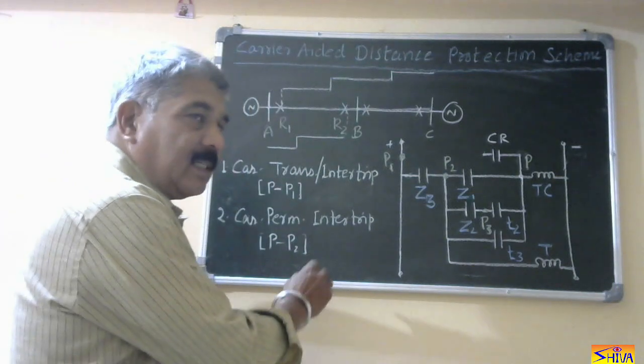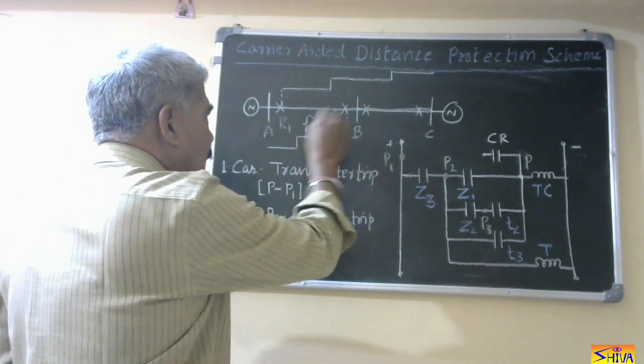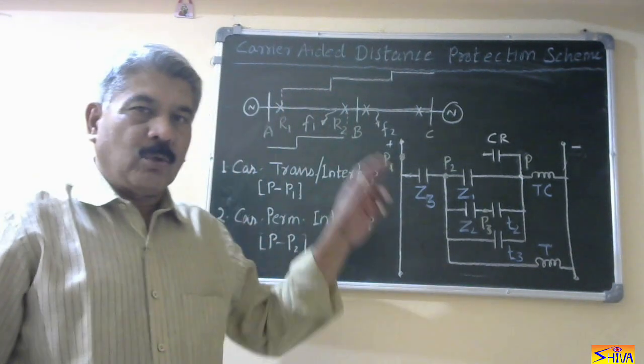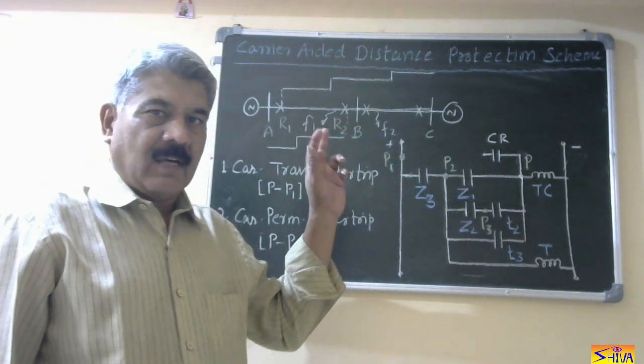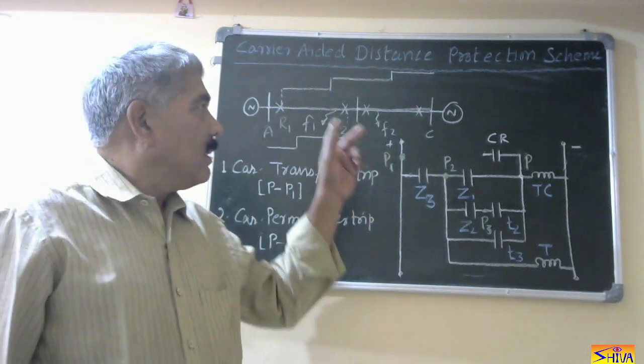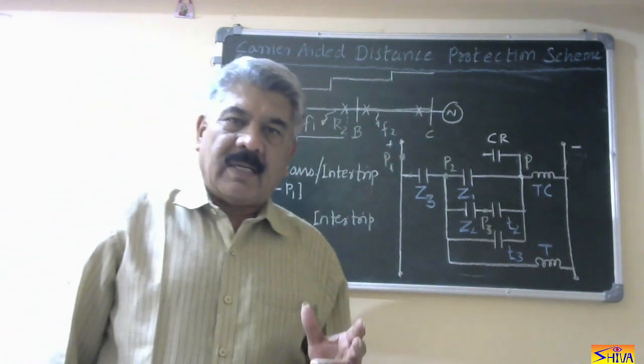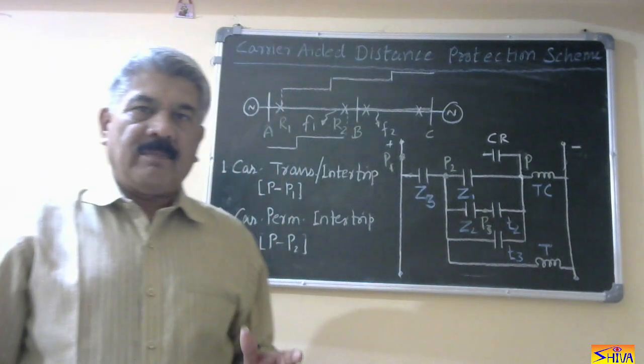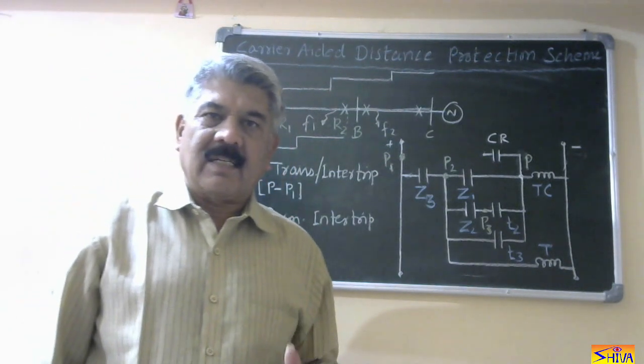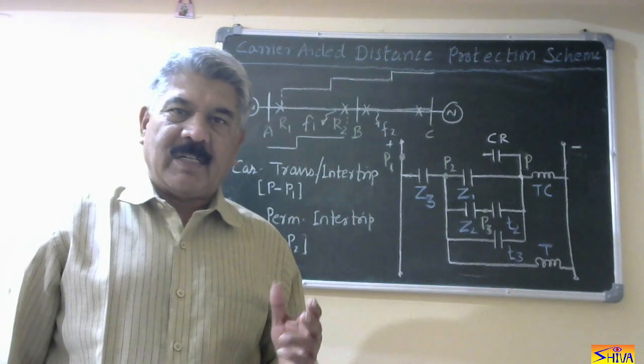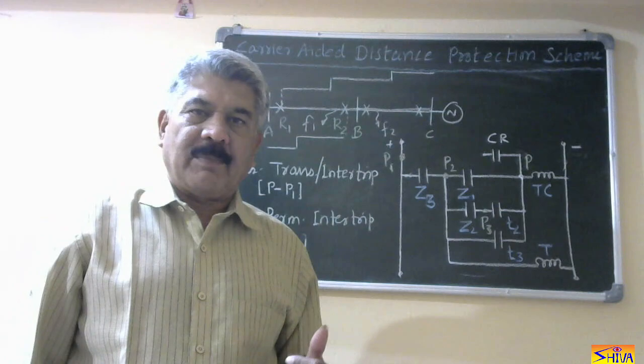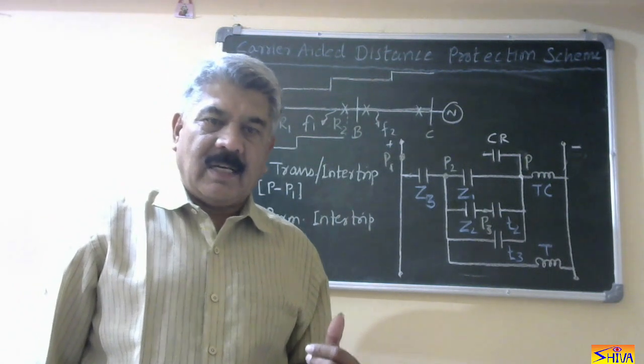Now let us consider two faults, F1 and F2. F1 and F2 both are in the second step of relay R1. The difference is F1 is an internal fault whereas F2 is an external fault. In the carrier-aided distance protection scheme, carrier signals — that is, very high frequency signals — are transmitted from one end to the other end in order to cause simultaneous tripping of the relay at both ends.